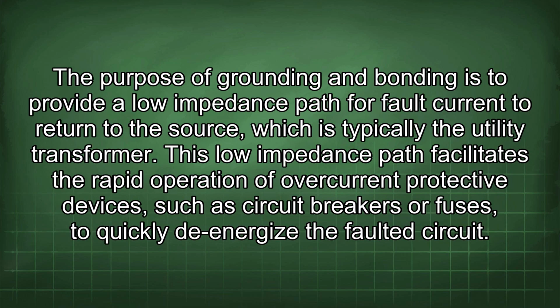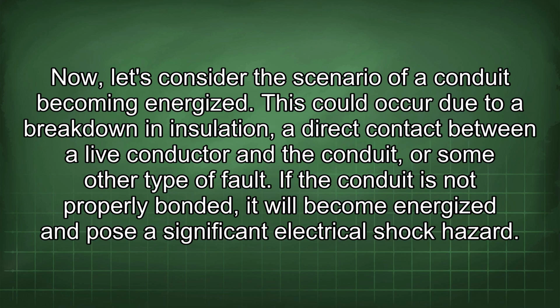The purpose of grounding and bonding is to provide a low impedance path for fault current to return to the source, which is typically the utility transformer. This low impedance path facilitates the rapid operation of overcurrent protective devices, such as circuit breakers or fuses, to quickly de-energize the faulted circuit. Now, let's consider the scenario of a conduit becoming energized.